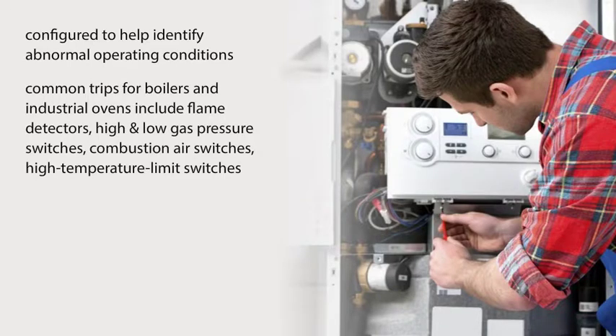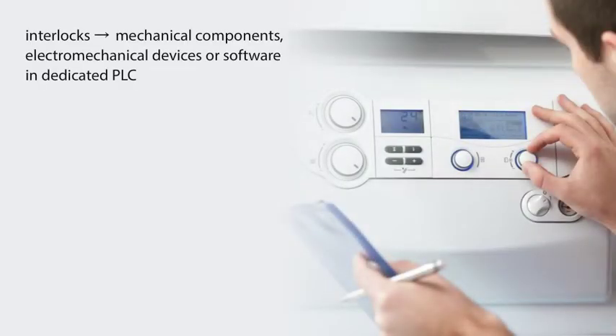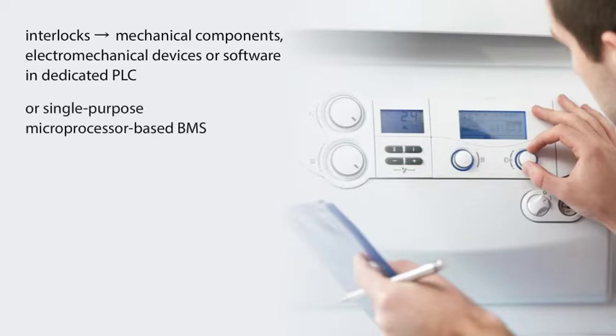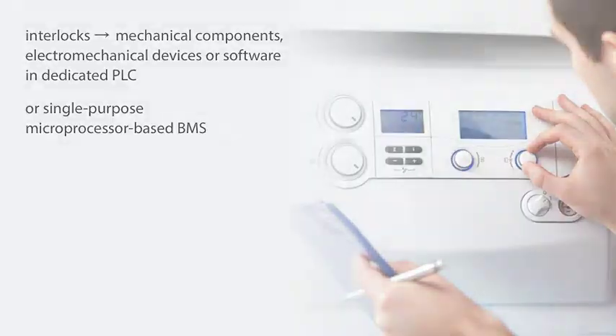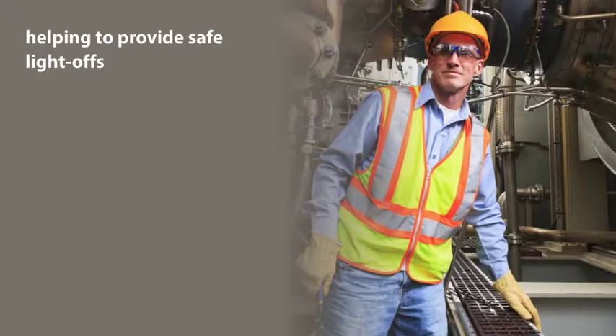Common trips for boilers and industrial ovens include flame detectors, high and low gas pressure switches, combustion air switches, and high temperature limit switches. Interlocks can be mechanical components, electromechanical devices, or software in a dedicated programmable logic controller, PLC. See codes for special requirements of PLCs that are used in safety applications and as BMSs, or a more traditional single-purpose microprocessor-based BMS.